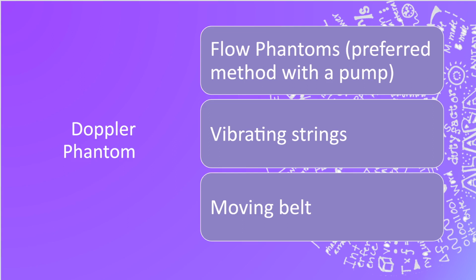The other couple things that are out there, a little bit older versions of phantoms, are vibrating string phantoms. Remember, the vibrating string is going to cause some movement within the structure so the machine can pick that up, or an actual moving belt, which can provide that Doppler shift so the machine can detect it. So again, Doppler phantoms have to have something that is moving within to test the Doppler function.